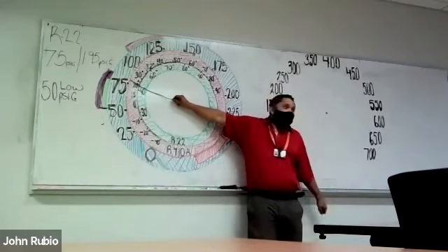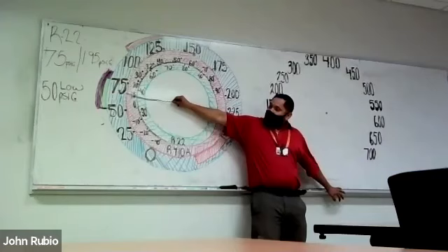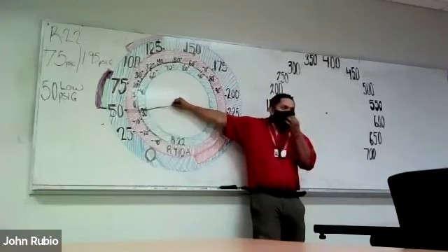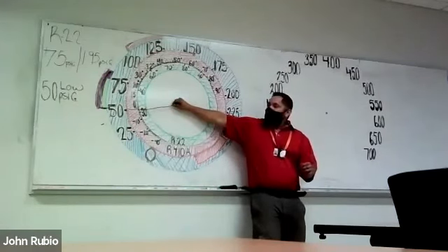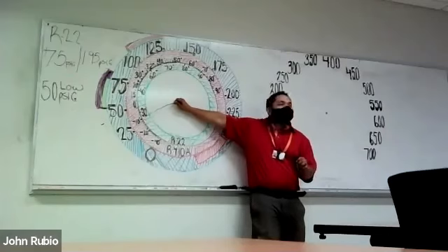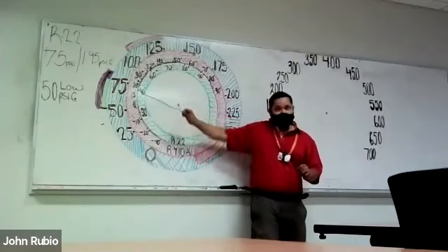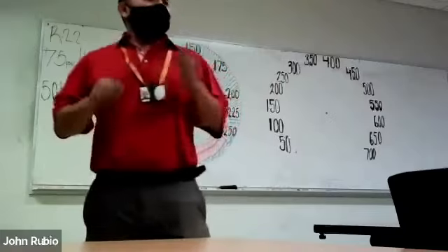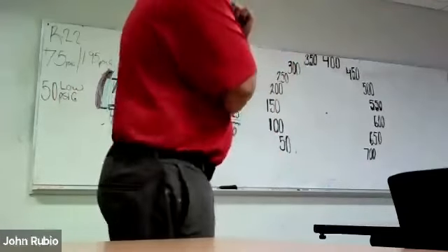Watch my green bar now as I slide down towards 50. Where am I in temperature? 32, 30 degrees. This is why once PSIG drops below 50, we're not guessing it's going to freeze up. We don't think it's going to freeze up. We are predicting and anticipating it is going to freeze up because it is below 30 on the temperature pressure chart. These are not just refrigerant gauges. These are temperature pressure charts, both of them.